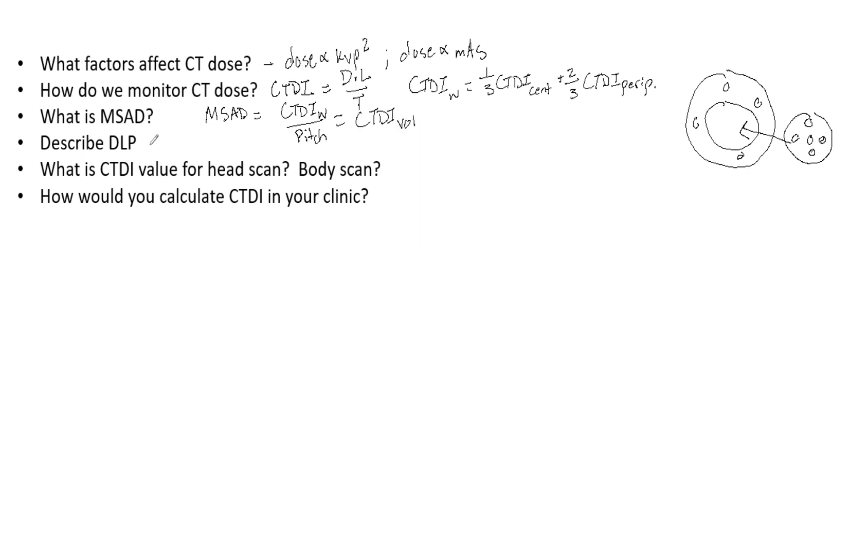So now what is DLP? I'm going to have to hop over here. DLP is the dose length product. This measures total radiation exposure from a series of scans. So the DLP is the CTDIVOL, and that is, again, similar to MSAD. It is the CTDI weighted divided by the pitch, and that's multiplied by the irradiation length.